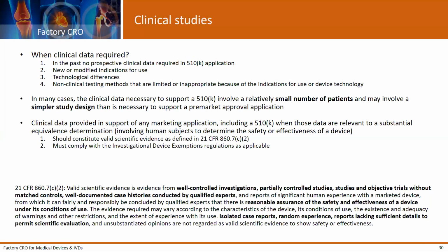In general, if you take a look at the FDA guidance documents, they are not necessarily looking for large clinical trials. They are expecting small studies with a relatively small number of patients and a simple study design, compared to the pre-market approval process, because this basically comes down to comparing your device to a device that is already approved and released to the market.